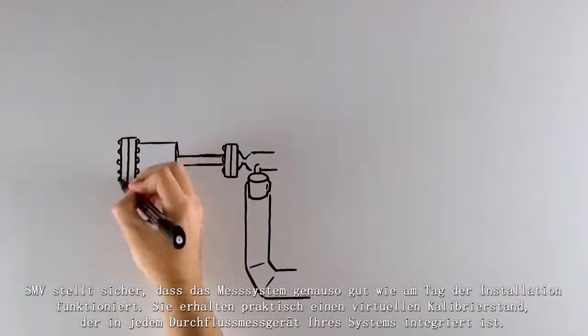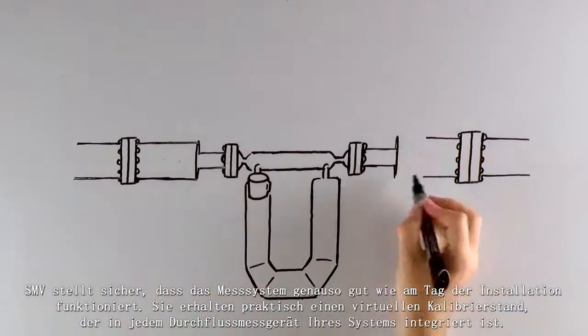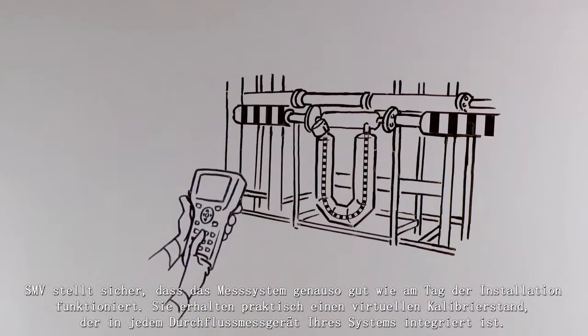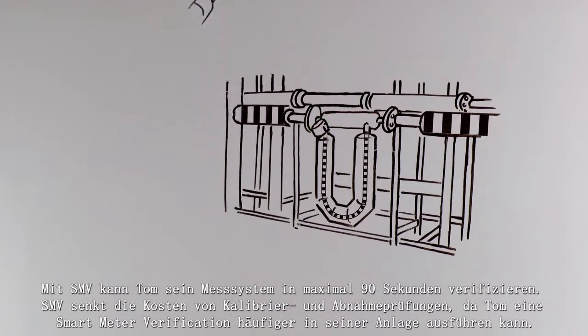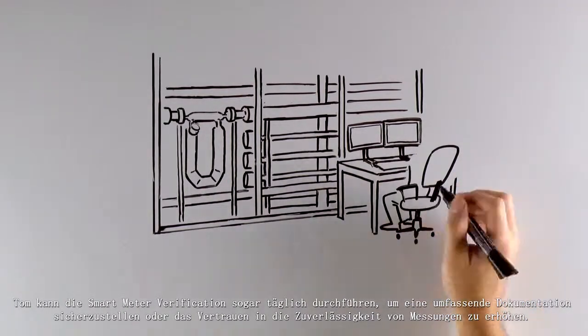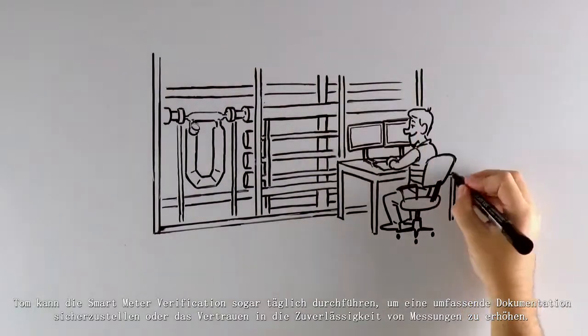SMV ensures that the meter is operating as well as the day it left the factory. It's like having a virtual calibration stand built into every flow meter in your system. With SMV, Tom can verify his meter in 90 seconds or less. SMV cuts the cost of calibration because Tom can run it more often within his plant. Tom can even run SMV daily to provide a robust audit trail or use SMV to bolster measurement confidence.